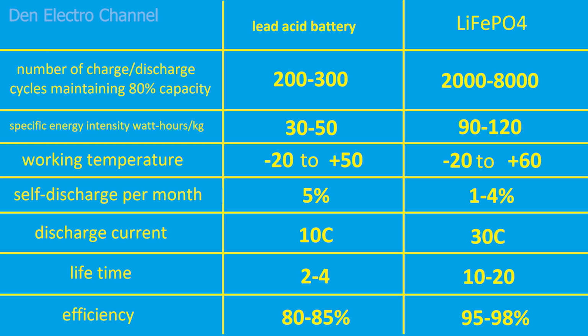A lithium iron phosphate battery will last for decades, and this is taking into account the fact that it will lose only a few percent of capacity. The degradation process will of course accelerate if the battery is cycled and drained every day. But in our case, naturally, this will not happen, since the battery is installed in an uninterruptible power supply and will be in buffer mode.